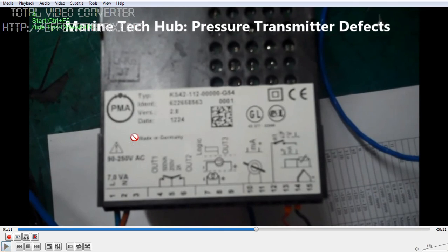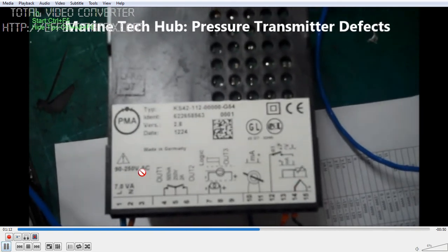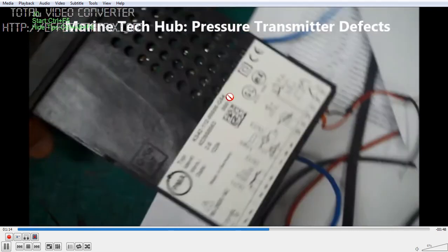This is the controller. We have 220 volts supplied here, and you can see the diagrams. The pressure transmitter has to be connected here, through which we get 4 to 20 milliamps, and that gives the pressure signal on the controller. There are other connections in the controller which I am not going to explain — I am only focused on the pressure transmitter signal here.